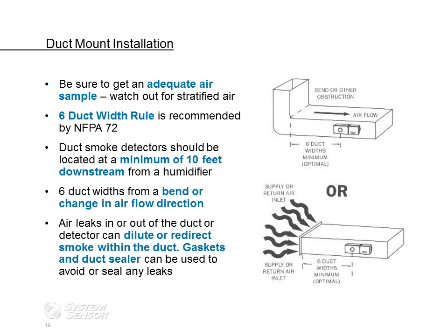Now this slide basically is going to cover some rules of thumb and some recommendations, and it's important that we understand that these are recommendations that we have for location and mounting of the duct detectors. One thing that we do have to do is be sure that we get an adequate air sample. So wherever the duct detector is mounted, we have to make sure that we're going to have a proper air sample because without proper airflow, the duct detector won't function correctly.